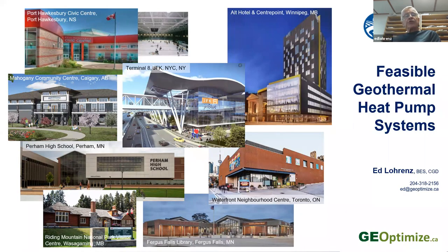So that, either cool it in the winter or warm the water in the summertime. And then you can use the well water without actually taking the water out of the ground. A bit less intrusive on the aquifer, and it can take advantage of the groundwater that way. It can be a little more cost effective in some cases than a closed loop system where you're burying plastic pipe in the ground. Or you can use it in combination with a closed loop system to help manage the temperature of the closed loop ground heat exchanger. So it's a pretty interesting system developed by some guys at the University of Minnesota.